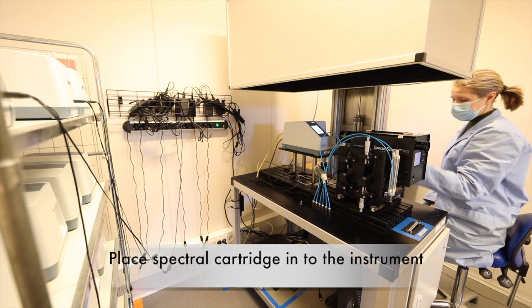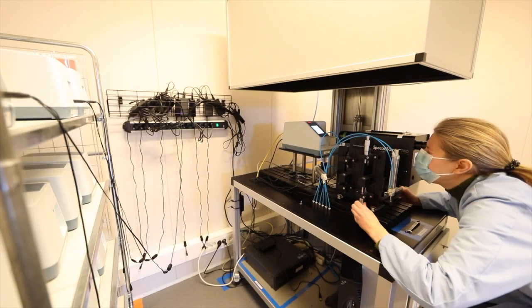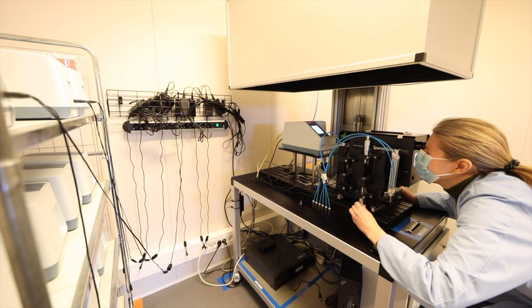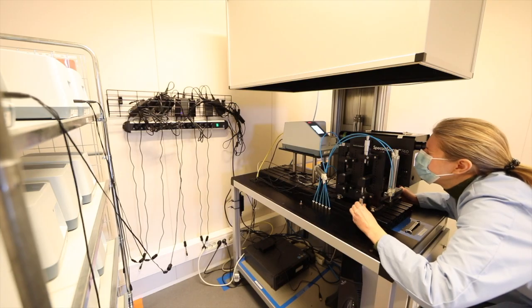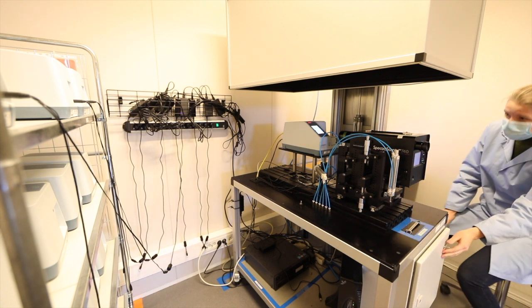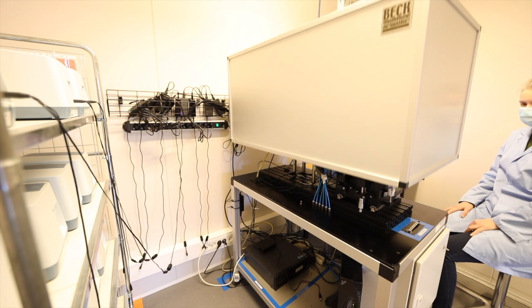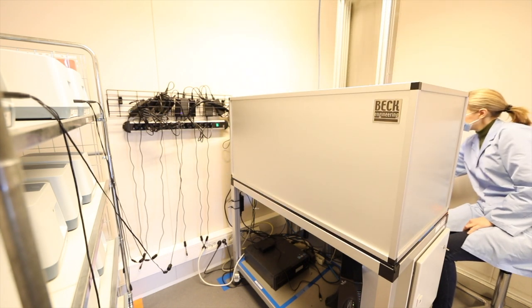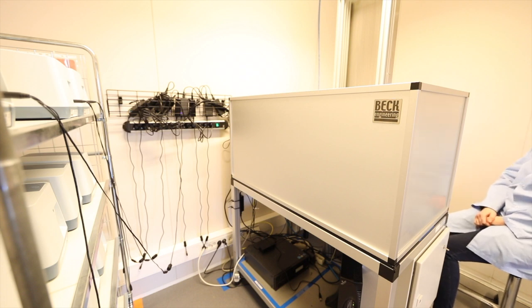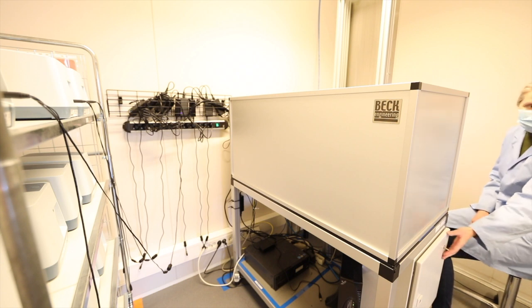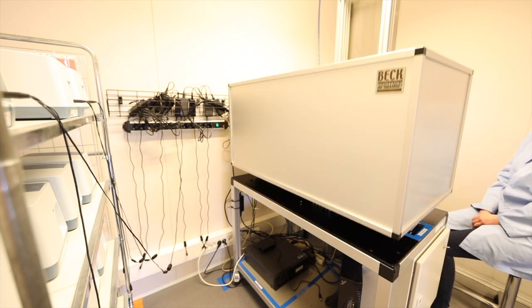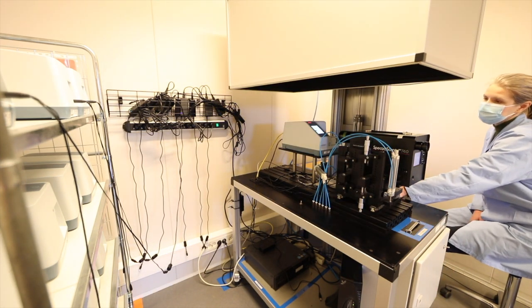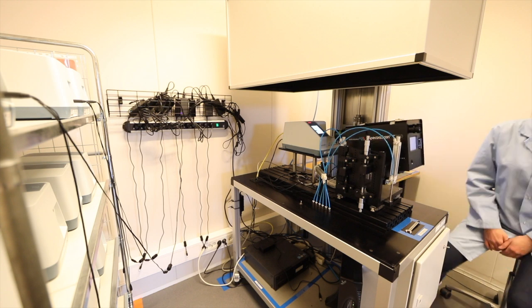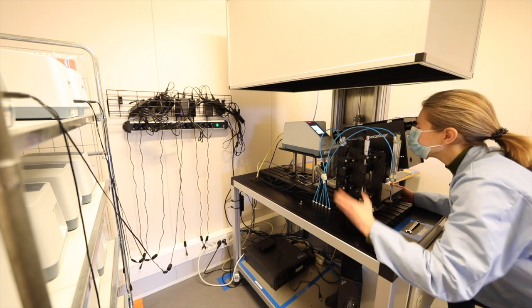Enter the spectral cartridge into the docking cavity and start the calibration. Focus the dots in the same way as you did with the reference instrument. Change the position of the SpectraScan to measure LED 3, 4 and 5. Focus the dot onto the center of the rectangle the same way as you did with the reference instrument. Close the lid, continue the calibration.